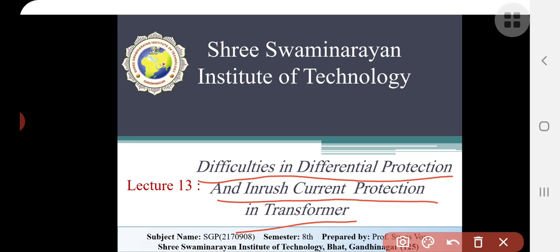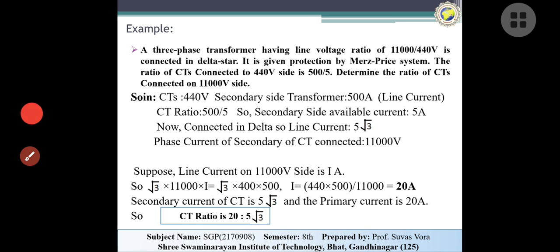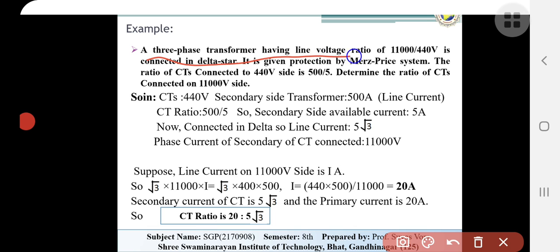So let us start with the topics. The first one is an example of the Merz-Price protection system. The example statement: a three phase transformer is connected in delta star and given Merz-Price protection. The CTs are connected to the 440 volt side, the secondary side, and the CT ratio is 500 by 5. So determine the ratio of CTs connected on the 11,000 side.